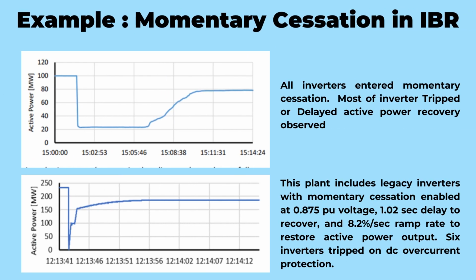Let me give you two examples of momentary cessation observed in IBR during a fault on a nearby transmission system. In the first example, when the fault occurred, all inverters at the plant entered momentary cessation. This means that most of the inverters either tripped or experienced a delay in recovering active power. As a result, there was a significant reduction in active power generation, and the recovery of active power was observed to be slow and significantly delayed. In the second example, the plant had legacy inverters that were designed with momentary cessation enabled at a voltage threshold of 0.875 per unit. In this case, when the fault occurred, the inverters entered momentary cessation mode and had a delay of 1.02 seconds before starting to recover active power. Additionally, the ramp rate for restoring active power output was set at 8.2% per second. Similar to the first example, the active power output was significantly reduced, and the recovery of active power was observed to be slow.